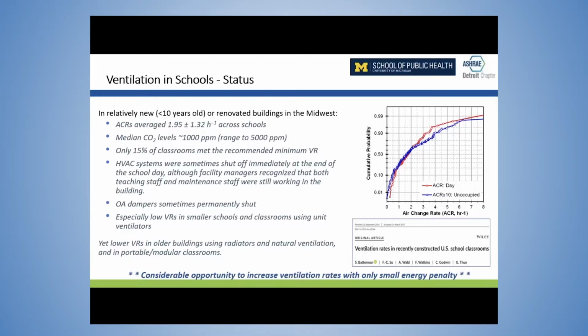On top of this, we found that HVAC systems, mechanical systems, were often shut off at the end of the school day, even though cleaning and other activities were still going on and folks were still working and sometimes kids were still present. We found a number of schools where the outside air dampers were permanently shut. We found particular problems in smaller schools and classrooms using unit ventilators and some simpler non-centralized mechanical systems. This was the status in newer buildings. When we're looking at older buildings, 20 to 50 to 60 years old, we find much lower ventilation rates, particularly in those schools using radiators and natural ventilation.